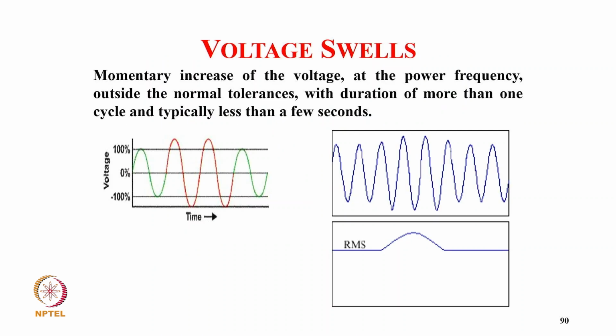The voltage swell is a momentary increase in the voltage at power frequency outside the normal tolerances, with a duration of more than 1 cycle and typically less than 3 seconds, as you can see here in the diagram.